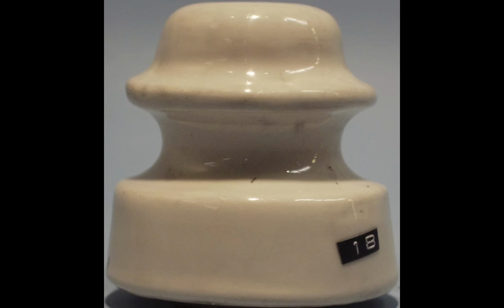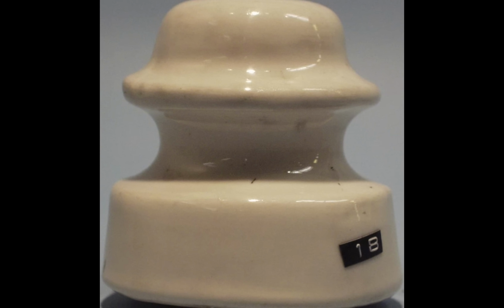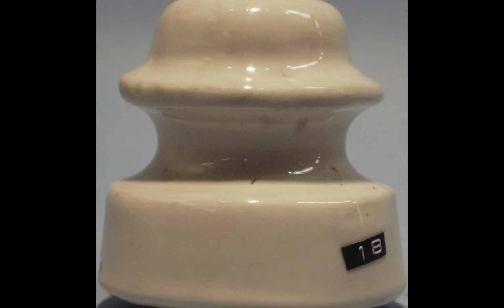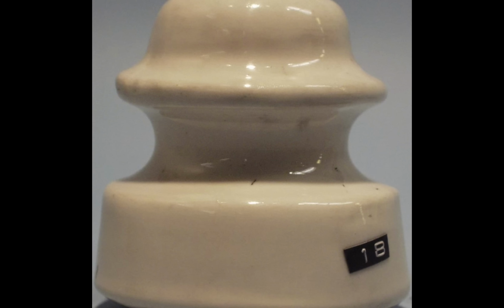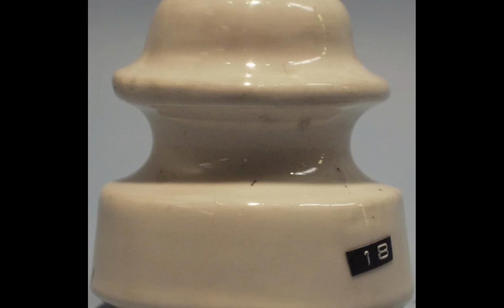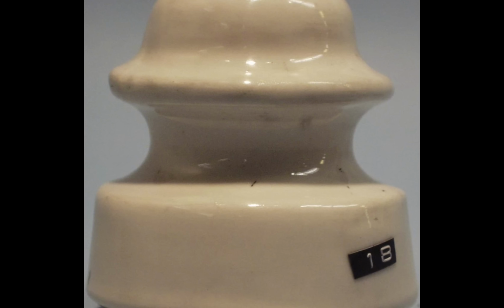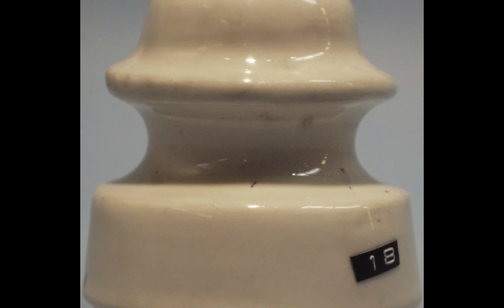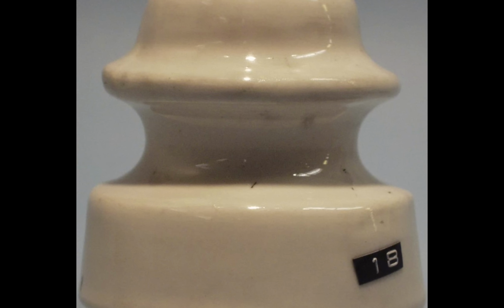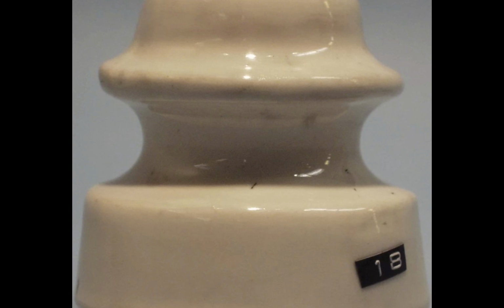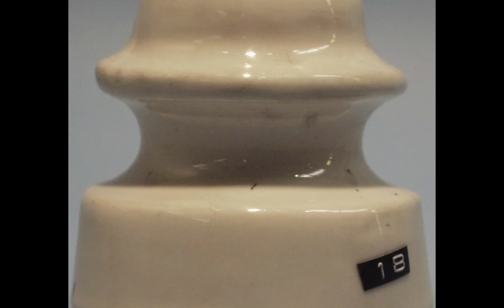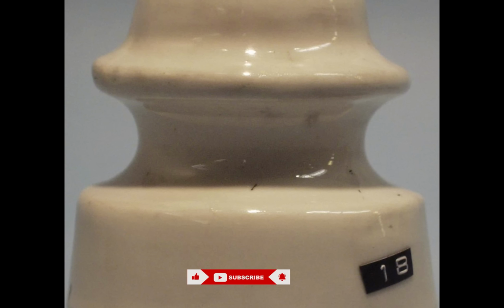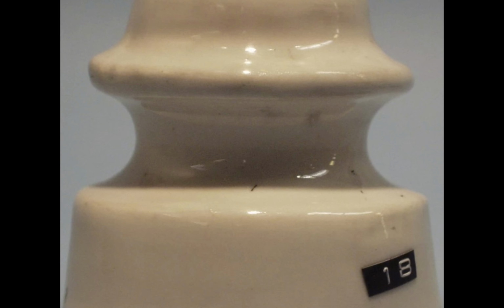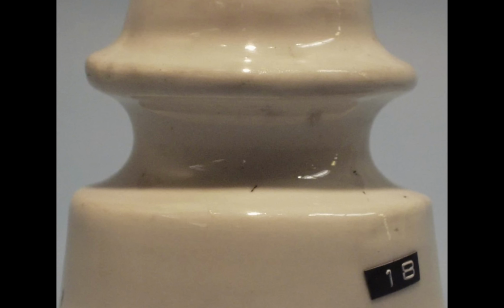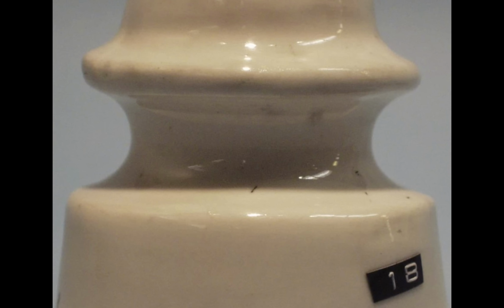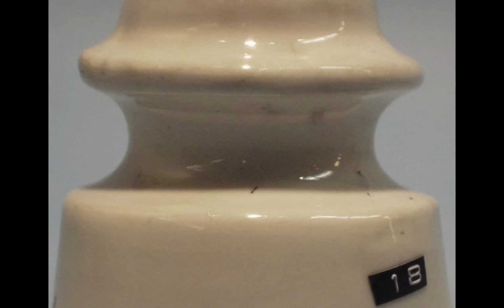The most obvious response to rising voltage was simply scaling the existing design up. Manufacturers added more porcelain shells, stacked vertically, to increase the surface distance current would have to travel to arc over. This worked, in a narrow sense. It did increase voltage resistance, but it also multiplied weight and wind resistance on a single rigid pin. And at 60,000 volts and above, the insulators became so heavy and top-heavy that they risked snapping their own mounting hardware in ordinary wind. The fix made the original mechanical weakness worse, not better.